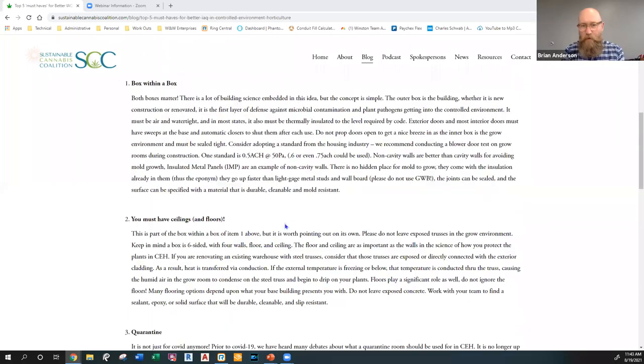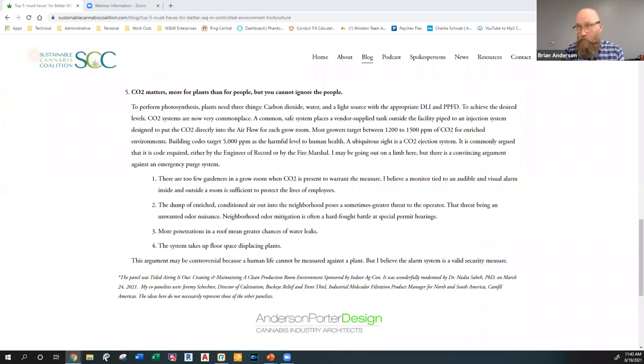So let's say, as an example, the room gets to 5,000 CO2 at midnight, nobody's in there, and we just cut off the CO2. That excess CO2 is still there. Are you saying it will be exhausted through the 0.5 ACH? What are your air changes? Does your primary mechanical system have the ability to pull that CO2 out, or will it dissipate naturally? That's a good question, I'd need an engineer to help me understand further.